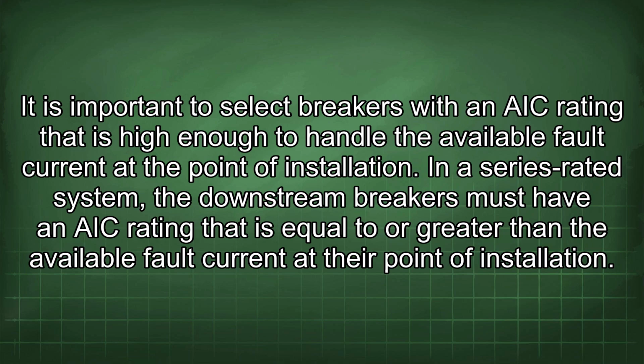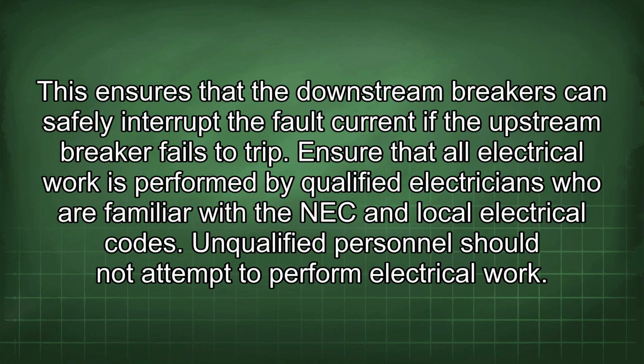In a series-rated system, the downstream breakers must have an AIC rating that is equal to or greater than the available fault current at their point of installation. This ensures that the downstream breakers can safely interrupt the fault current if the upstream breaker fails to trip.